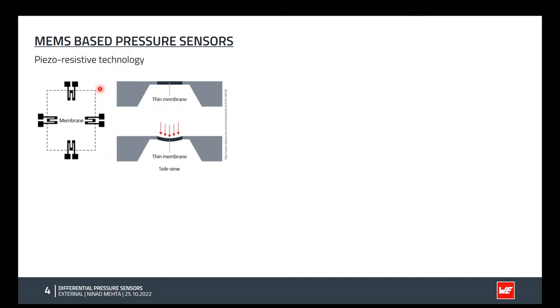So basically what we do here is that we have a silicon substrate, which is etched from the backside, and with a chemical etch stop layer, we can stop the etching so that we have a very thin silicon membrane. On the top side, we have a thin membrane which is suspended in the air, and on the edges we dope the piezo resistors. So we have the piezo resistors doped on the suspended silicon membrane, and whenever there is some force or pressure applied on top of the membrane, which is very thin, even a very small deviation can cause a deflection in the membrane, and that's why the piezo resistivity of the piezo resistor will change. The material will be under compression or tension, depending on what direction the pressure has been applied.